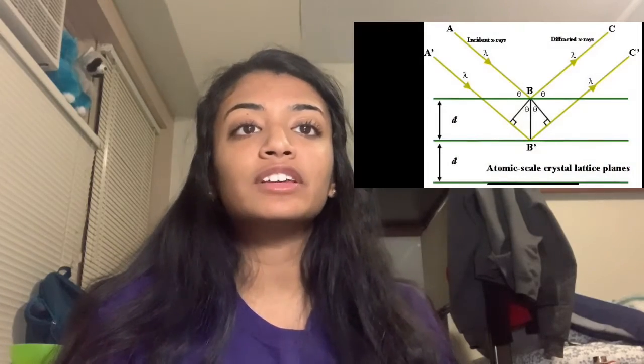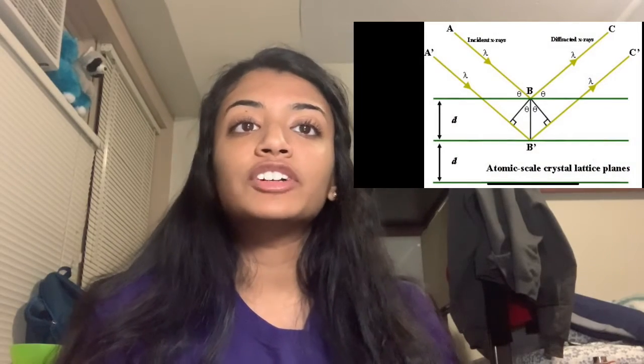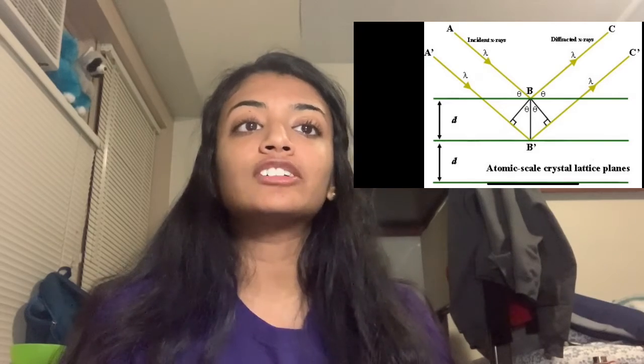In X-ray diffraction, XRD, the interplanar spacing, also known as the d-spacing, of a crystal is used for identification and characterization purposes. D-spacing is the distance between successive parallel planes of atoms. In this case, the wavelength of the incident X-ray is known, and the measurement is made of the incident angle at which constructive interference occurs. Solving Bragg's equation gives the d-spacing between the crystal lattice planes of atoms that produce the constructive interference.